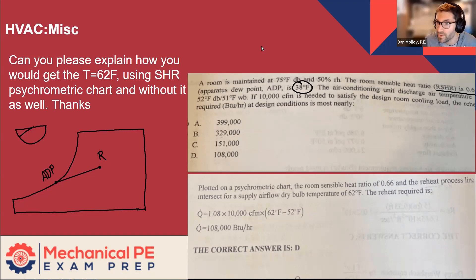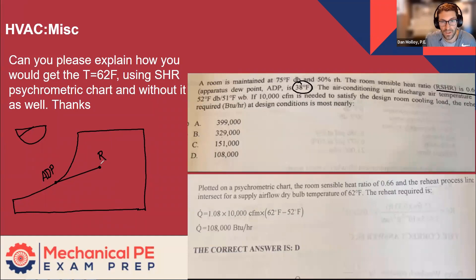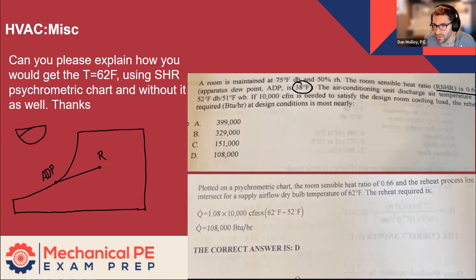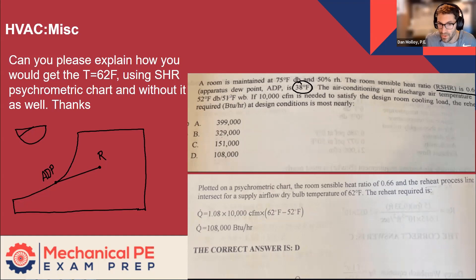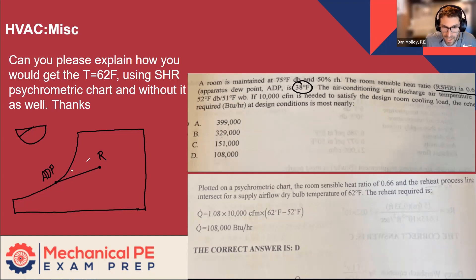I'm going to switch colors now and draw what's actually happening with this system, which is kind of unique — the system is using reheat. There's a supply air condition of 52 degrees dry bulb and 51 degrees wet bulb. So if the ADP is 38 and the supply is 52 DB / 51 WB, it's going to be somewhere over here — lower than where we started. We'll have a diagonal line, but not quite the same slope, and it's not going to go as far down.